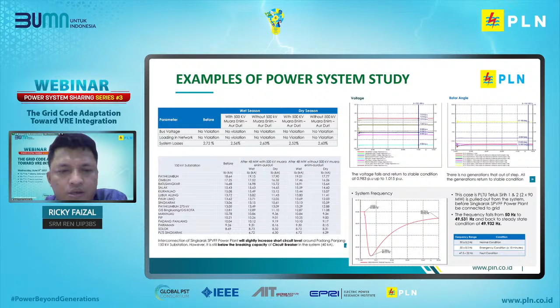This is the system stiffness of the Sumatra grid. As we can see in peak hour and off-peak, we calculated this using the realizations of the disturbance. For peak hour, our system stiffness is around 260 megawatts per hertz, and for off-peak hour, it's around 245 megawatts per hertz.